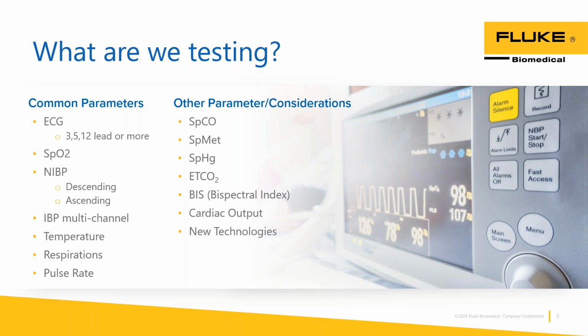End-tidal CO2, BIS or bispectral index, cardiac output. Plus, there are so many new technologies coming out these days that we couldn't even think to list them on this. Are you familiar with all of them? Do you have the capabilities of testing all of them? And what parameters do your monitors have on them? And with that, we go back to, again, if your monitor has it on it, just because of the area it's in in the hospital, it might not be used there, but there's a chance that module could get moved to another department. So are you testing that parameter anyways? Because there is a potential for that monitor to go from point A to point B.